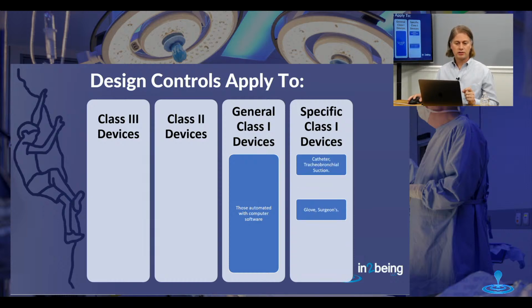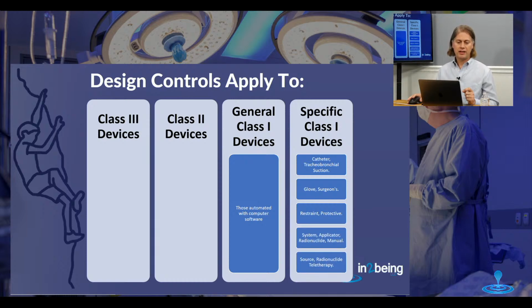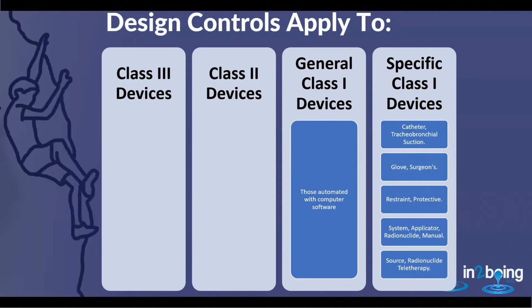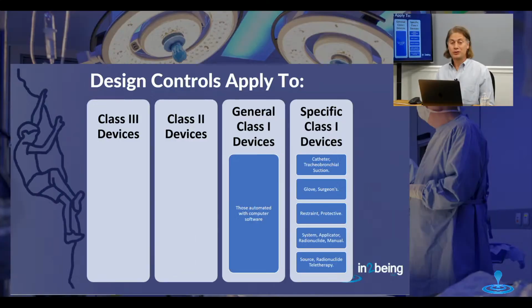There's also five specific categories of Class 1 device that are subject to design controls. It's a very eclectic list. A tracheobronchial suction catheter, which happens to be Class 1 but subject to design controls. A surgeon's glove, which is Class 1 but subject to design controls. A protective restraint, again Class 1 but subject to design controls. A manual radionuclide applicator system, and a radionuclide teletherapy source.